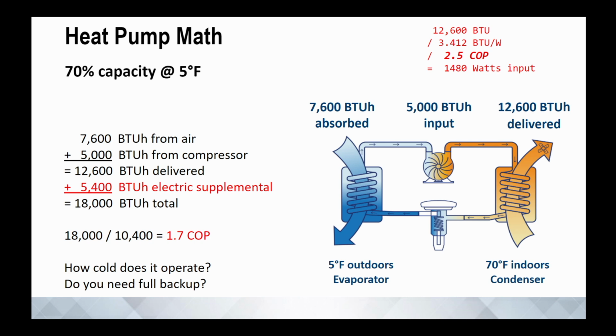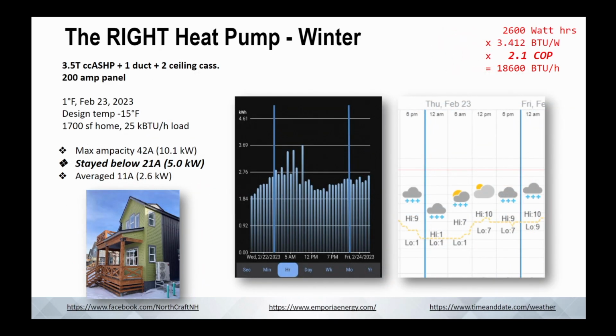But now we have to account for that extra energy, right? And so when we add this up, the 5,000 from the compressor plus another 5,400 from the supplemental, we're hitting 18,000, but our efficiency is 170% instead of the 250% that we bought and paid for from the contractor that said, oh yeah, 70% efficient heat pump, it's going to be great. We'll just put on this extra thing just in case. Well, just in case is happening at 5 degrees, which is actually warmer than our design temperature, and we see that temperature, not all the time, all winter, but we're going to see it a lot. And you're going to be paying a lot more. You're not really getting what you're paying for, in my opinion.